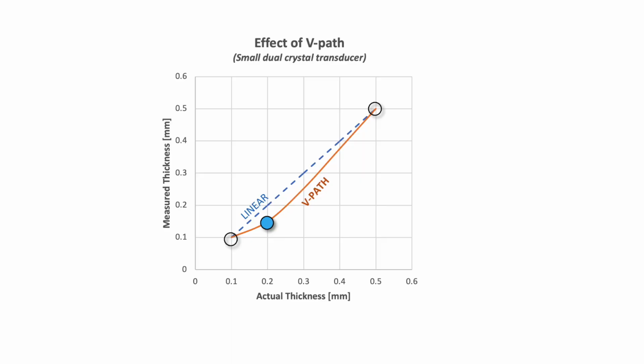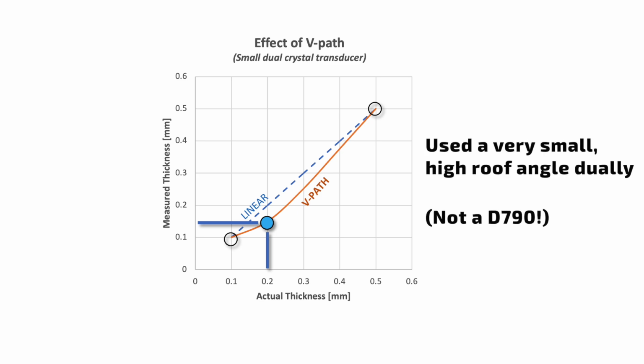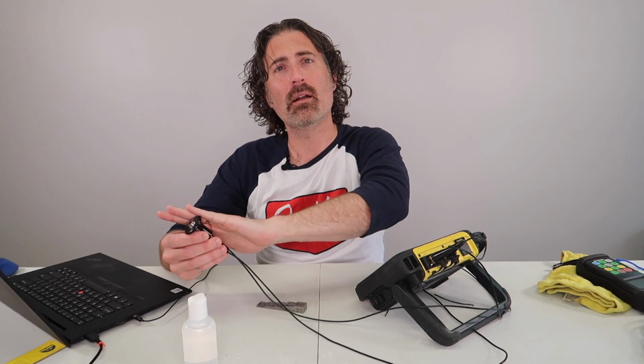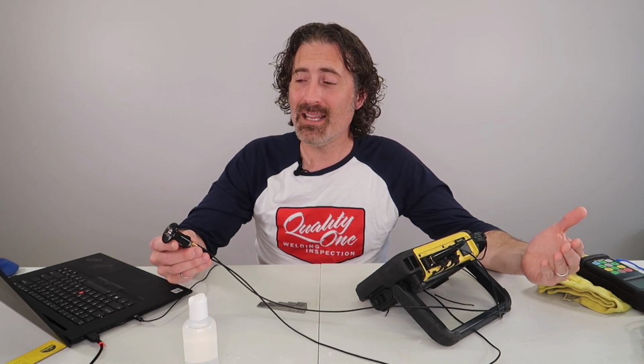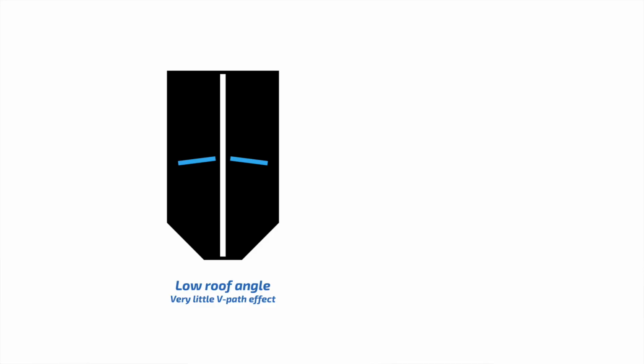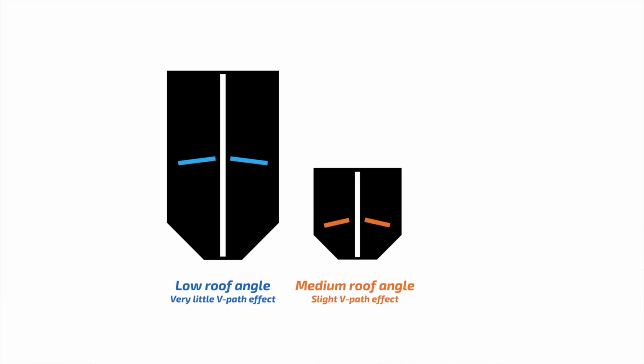Then I took readings at every intermediate step on the wedge, and you can see here that at an actual thickness of 0.2 mm, the machine reads 0.15 due to the V-path. The V-path error is proportional to the roof angle, but it's really difficult to try to find what the roof angle is of your probe. The dead giveaway is how tall is it? A D790 is pretty tall, so it's got a pretty low roof angle and very little V-path error. Once you get to smaller probes, you end up with more of a tilt, more of a roof angle between the transmit and receive sides, and then you get a lot more V-path error.